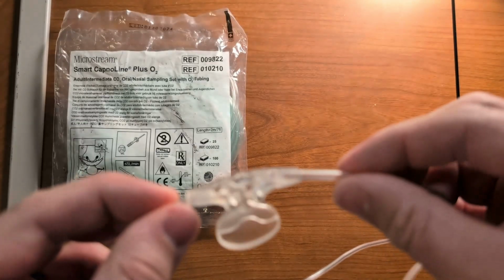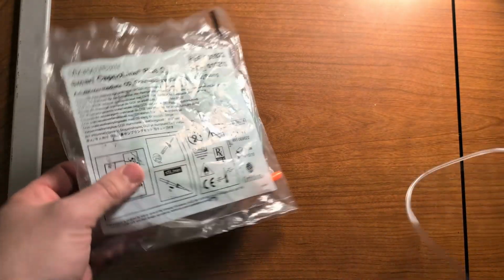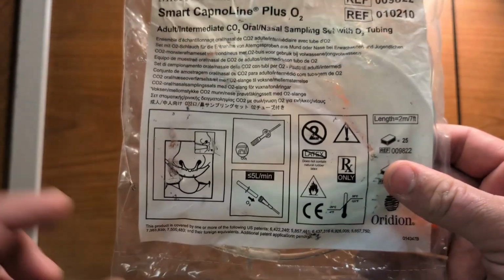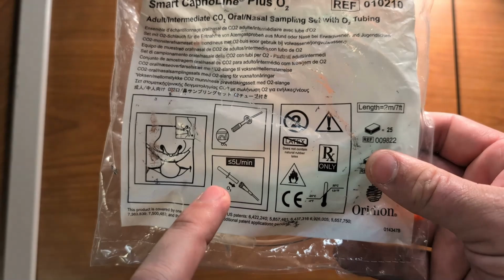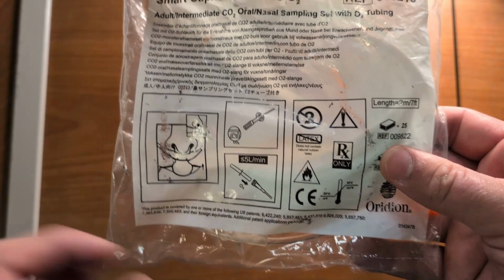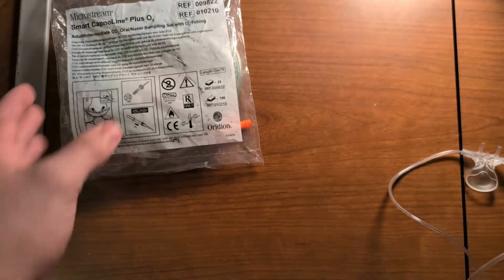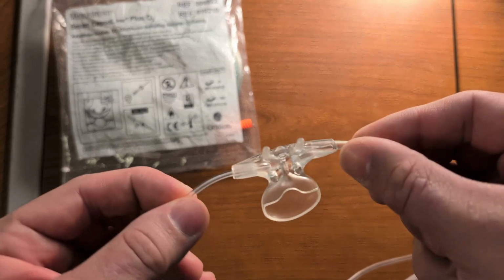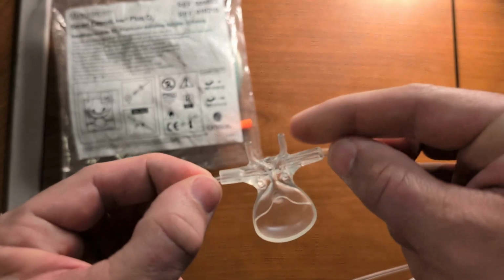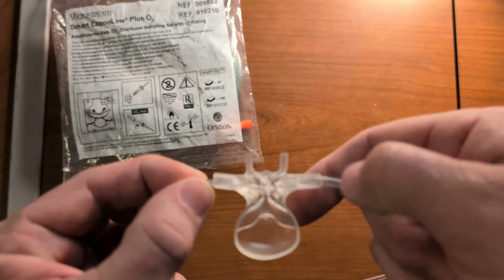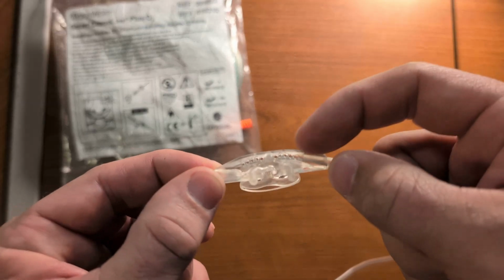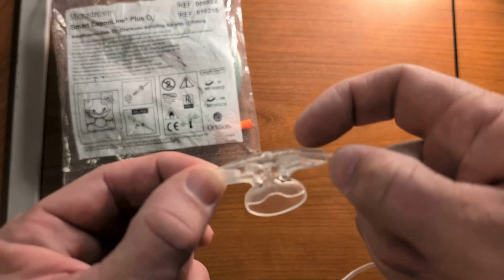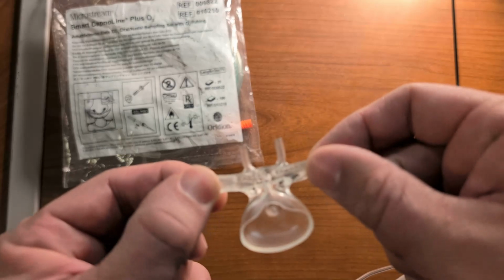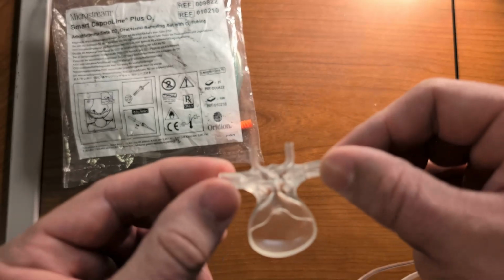One of them is just flow rate. If you look on the packaging, it'll actually tell you you've got to have less than or equal to 5 liters per minute for this to get an accurate reading. More than that is going to wash away the end-tidal CO2 that would have been picked up by these sensors here. So if we start blasting oxygen through here, it's going to displace some of that end-tidal CO2 that we would have been able to pick up.